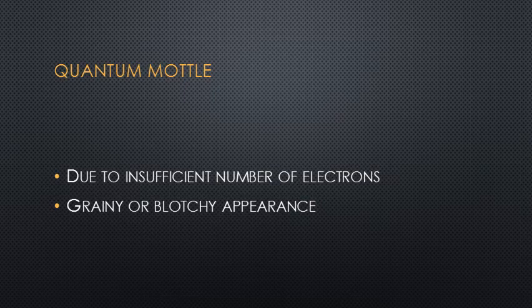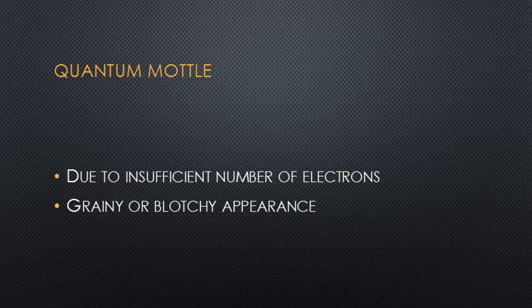Other factors that change the brightness of the image, in addition to radiation output, include the ability of the eye to adjust to brightness, subject beam attenuation factors, the conversion efficiency of the input screen itself, the flux gain, the brightness gain, and the viewing system monitor. It also accounts for the distance between the display screen and the person viewing the monitor. All of these factors contribute to the appearance of mottle, but the main solution is to increase the MA.